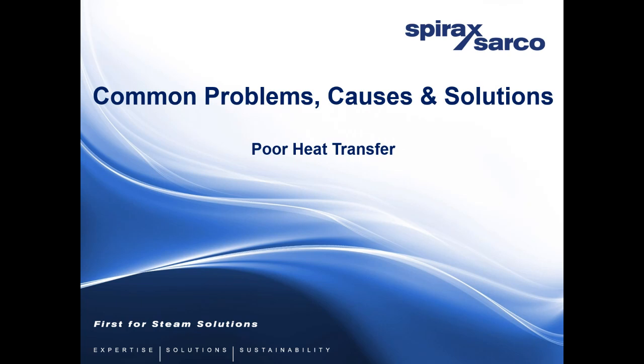Maybe I can also go to the next question, what's the best practice in relation to checking the effectiveness of steam traps to avoid loss of steam through failed steam traps? There's a few ways you can do it. We'll start at the cheapest, the easiest. If you have a sight glass in your condensate system, you can see if you have condensate passing through your line instead of steam. That can be an indication your trap is working correctly. If you see nothing, you can tell that the trap is failed closed.